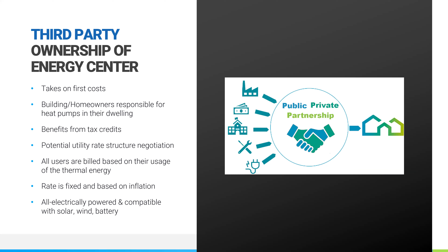One of the big benefits, particularly in the US, is that people like choice in what they put in their home or building. By going with a condenser water system and having each individual home, building, or school interconnect with it, you leave the choice with the homeowner on what type of HVAC and heating system they want. If they're used to a forced draft furnace, they can go with traditional water to air heat pumps. If they want radiant heating or cooling, water to water heat pumps work. If they like wall mounted mini split fan coils or the concealed look of VRF, they can go with a water source VRF system that provides the same benefits.